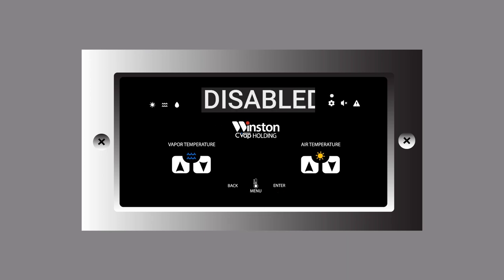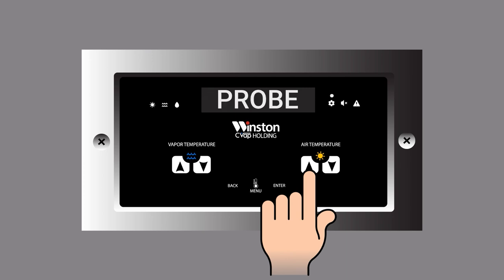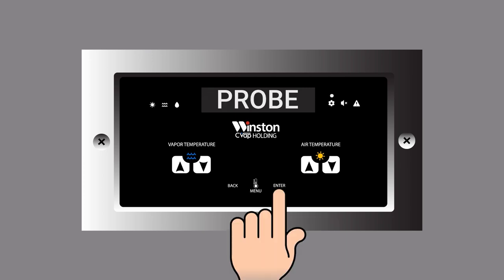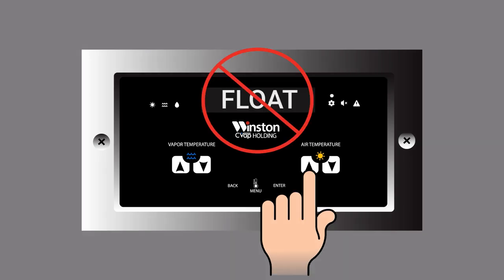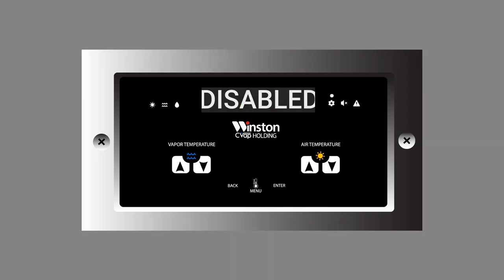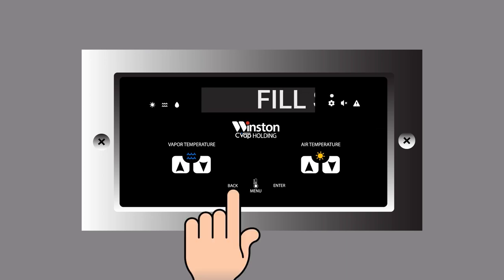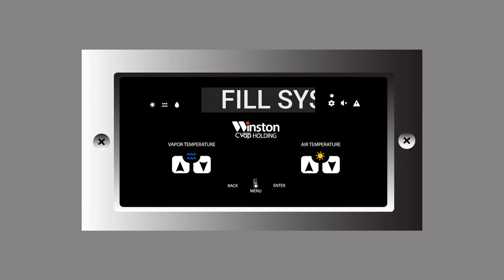If the drawer has low water detection, use the air temperature up and down button, set the level sensor to probe, and select Enter. Do not set the unit to float. If the drawer doesn't have low water detection, or if you want to disable the low water detection, set the level sensor to disabled and select Enter. Level sensor will be displayed. Select Back button. Fill system will be displayed.